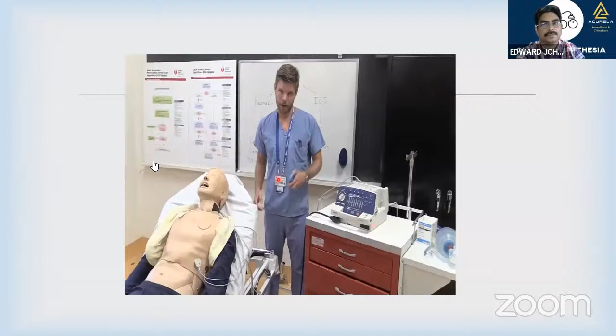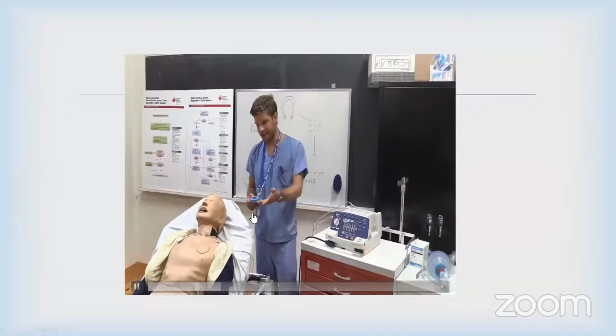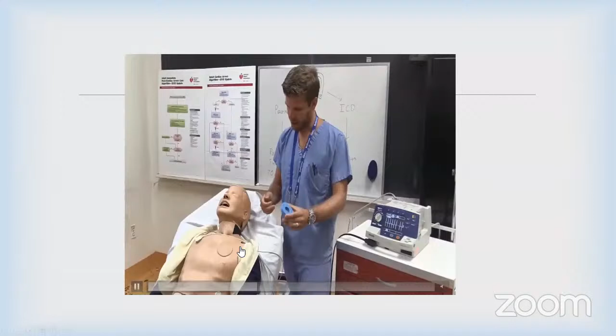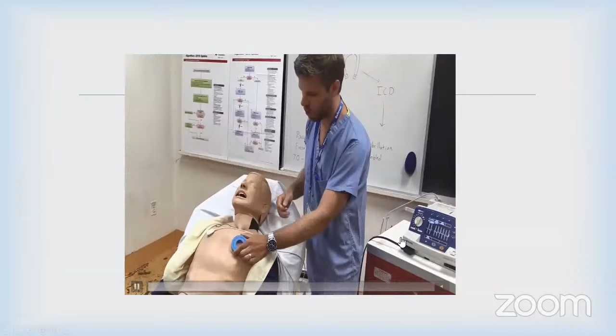Here you can see the patient has got a high risk, high mode. Now, you keep the magnet and simply place the magnet over the scar, and it goes into asynchronous mode of 60 to 80, whatever you have set. Right, it is 80 beats per minute. The moment you remove the magnet, it will go back to its original mode. It takes hardly 1 or 2 seconds to convert.